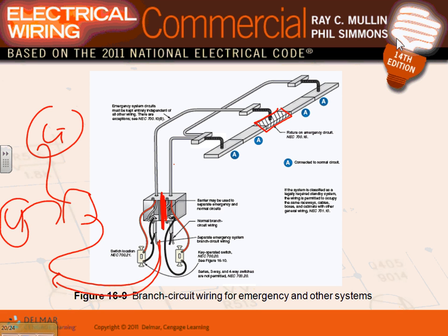In 2011, there's another way, guys, where inside this fixture itself, you will have a relay. On the relay, you're going to have a circuit coming from the normal and a circuit coming from the emergency.